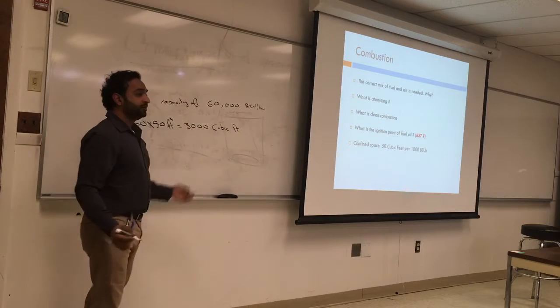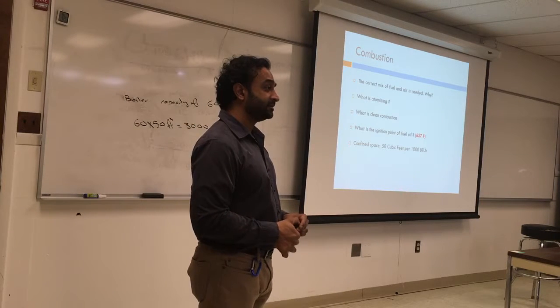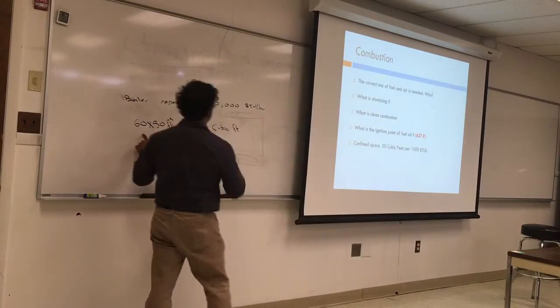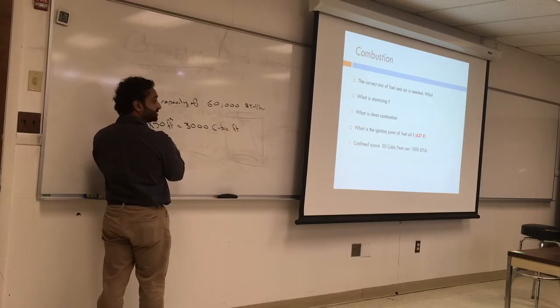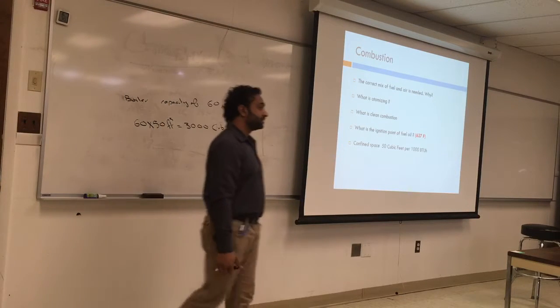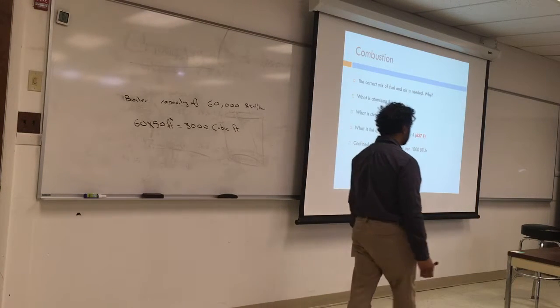If I have 2,500, that is confined or non-confined space? That's confined space. Confined means small, tight place. Because this is 60,000. For each 1,000 you want 50. So 60,000, 60 times 50. For each 1,000 that will give you 3,000 cubic feet. Make sense? We'll do a few examples about that.